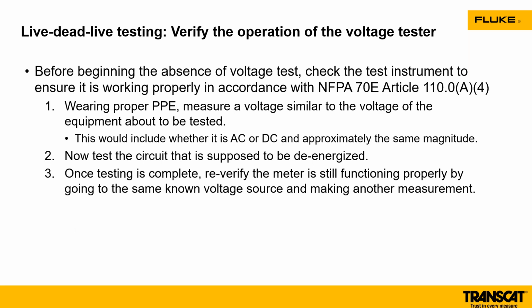How we can do this is by going through a live dead live test. This is also part of NFPA 70E. We want to do a live dead live test on our meter. This is where we turn the meter on, we do a voltage measurement, we turn that source voltage off, we do another test, we validate that the meter is reading 0, and then we turn that source voltage back on and validate that it's reading the voltage, whatever that may be. That's a good live dead live test. We've verified that the meter is working and functioning correctly, and we know that you're going to be safe when you go out there.